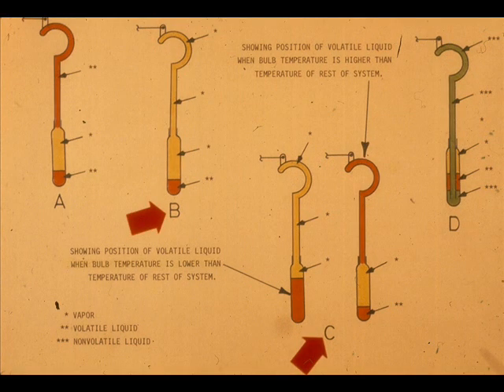Class 2C must always have the bulb and case at the same elevation. Class 2B needs no static head correction at all because all the liquid is in the bulb.